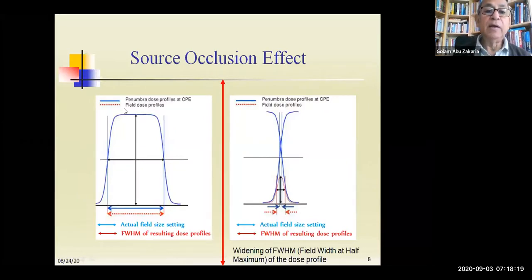You see when you have a large field, then the actual field setting through the collimator is equal to the FWHM of the resulting dose profile. That means when you measure the field size with the profile and the setting of the collimator, they are the same. But in a small field it is not. You see the collimator setting is less than the measured field size through the dose profile. That's why we should always measure the dose profile and use some lookup table in the protocol.